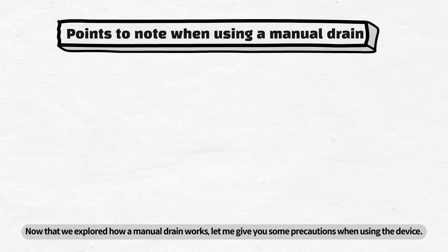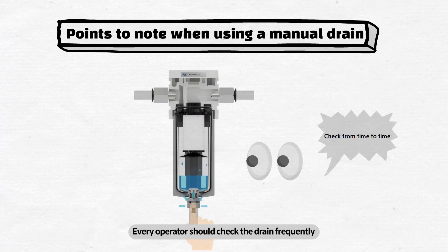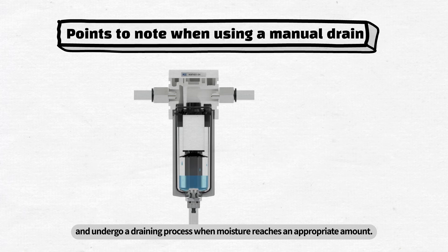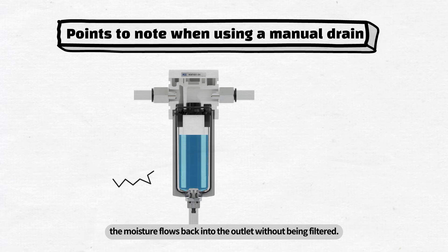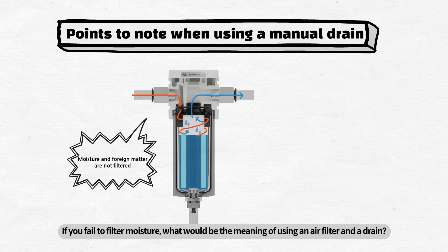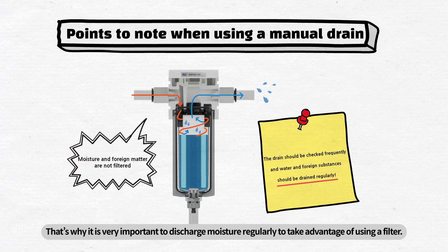Now that we explored how a manual drain works, let me give you some precautions when using the device. Every operator should check the drain frequently and undergo a draining process when moisture reaches an appropriate amount. If you miss this process and leave the drain to accumulate moisture inside, the moisture flows back into the outlet without being filtered. If you fail to filter moisture, what would be the meaning of using an air filter and a drain? That's why it is very important to discharge moisture regularly to take advantage of using a filter.